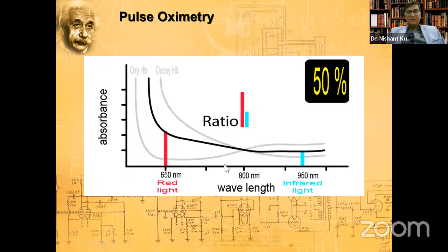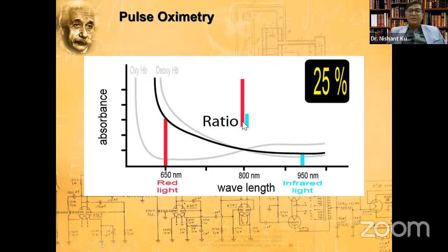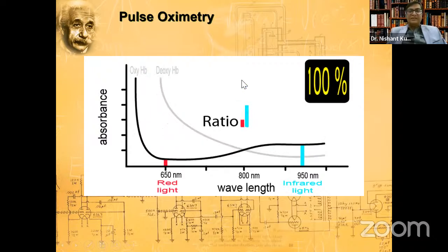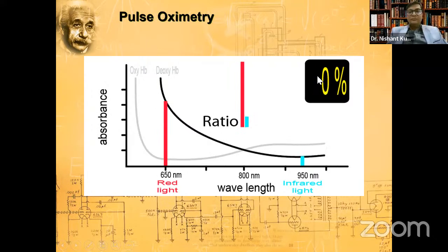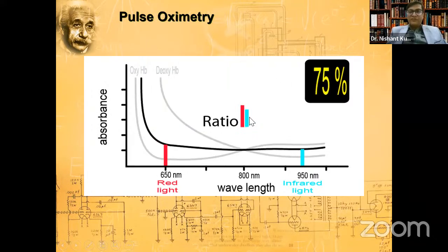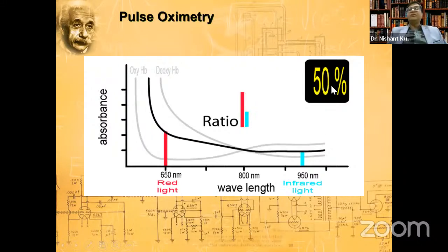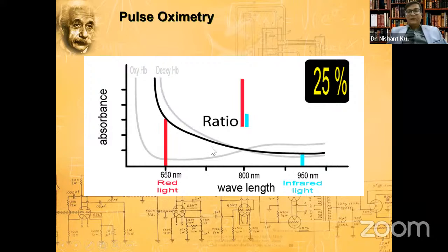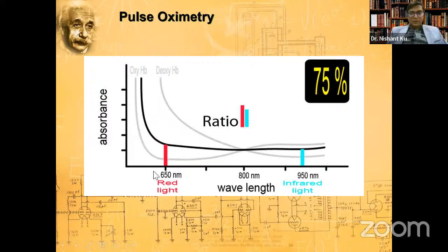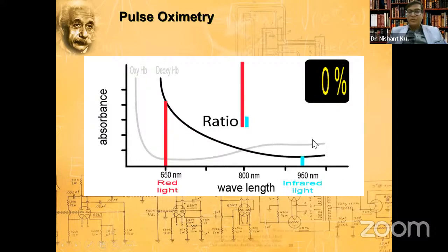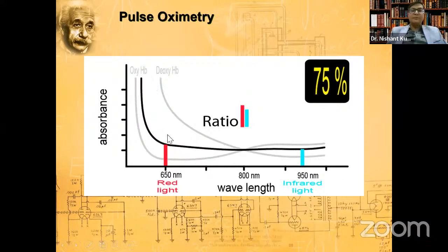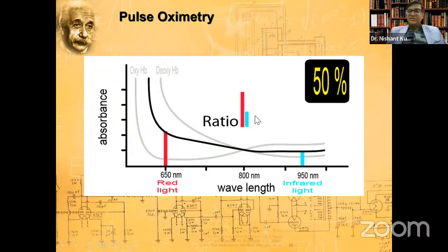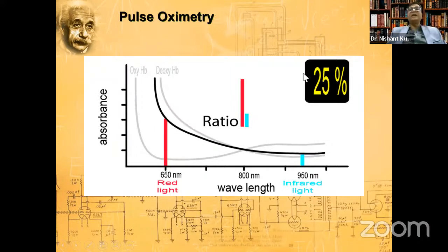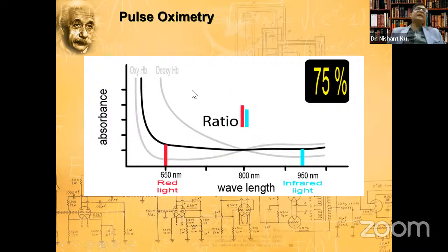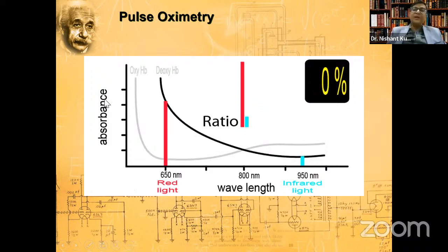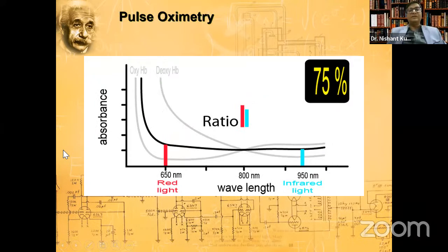Now, this is a very nice graph. As the absorption of red light increases, the SpO2 is falling, right? As the absorption of infrared light is increasing, the saturation is increasing. As I said, oxyhemoglobin absorbs more infrared light and deoxyhemoglobin absorbs more red light. So basically, it is the ratio of the absorption of red light and infrared light which is displayed by the pulse oximeter, and in turn tells us how much deoxyhemoglobin and how much oxyhemoglobin is in the capillaries in the fingers.